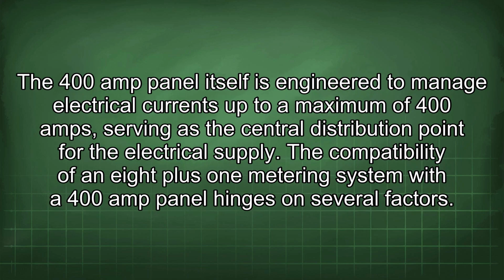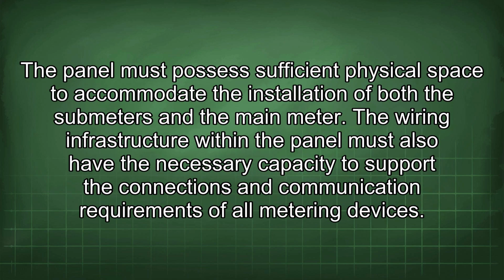The 400 amp panel itself is engineered to manage electrical currents up to a maximum of 400 amps, serving as a central distribution point for the electrical supply. The compatibility of an 8+1 metering system with a 400 amp panel hinges on several factors. The panel must possess sufficient physical space to accommodate the installation of both the submeters and the main meter.